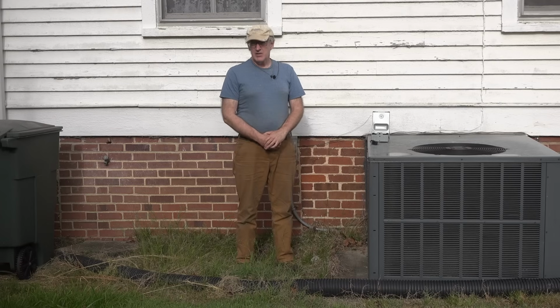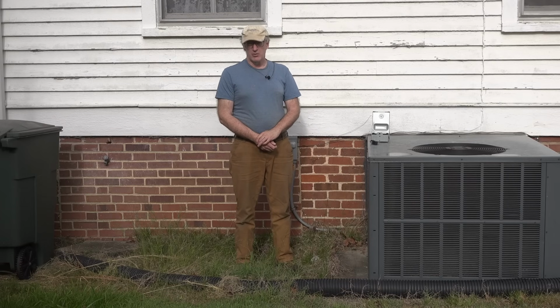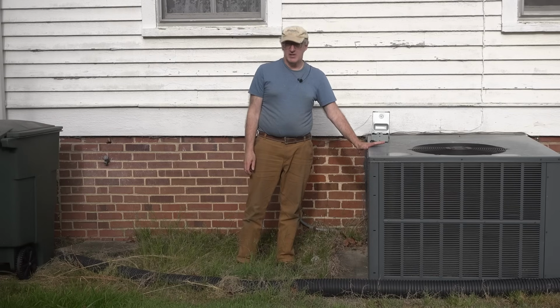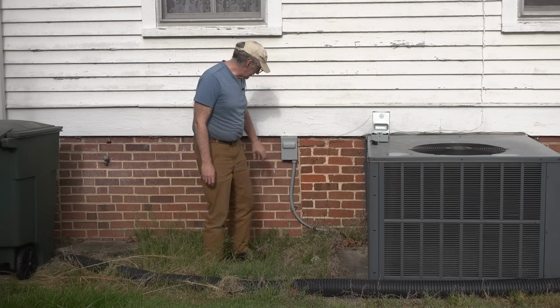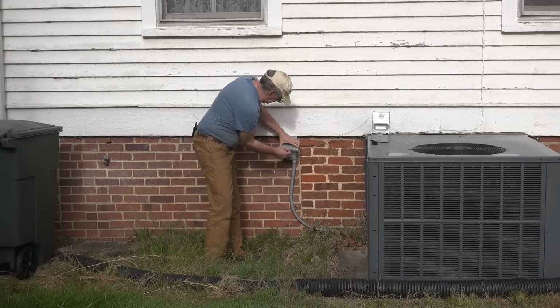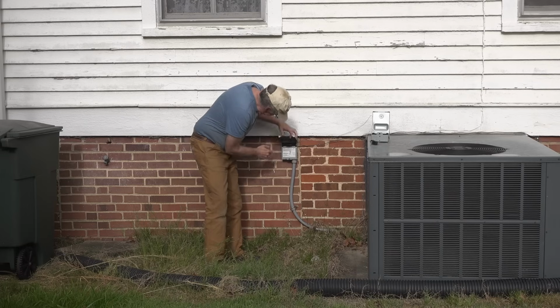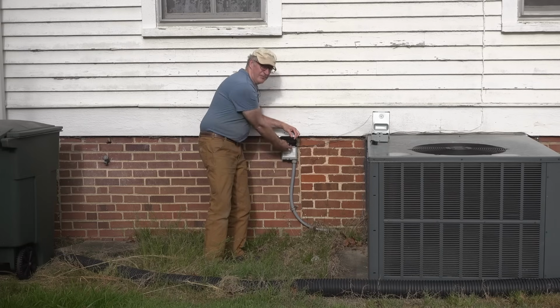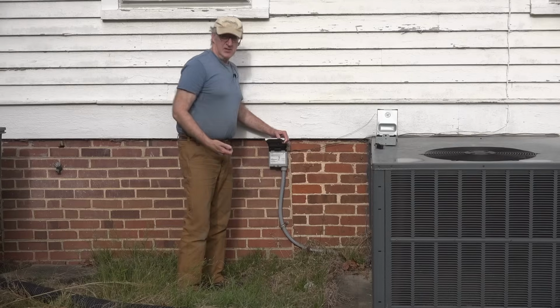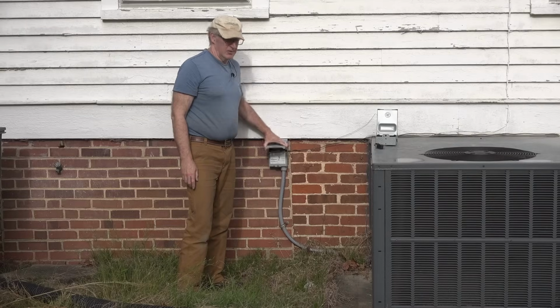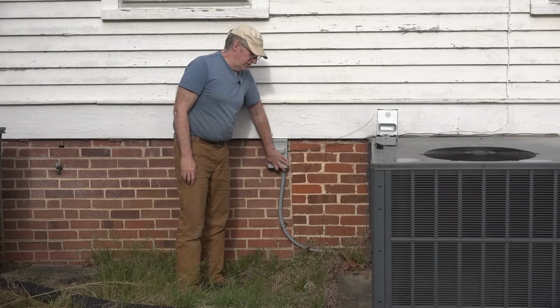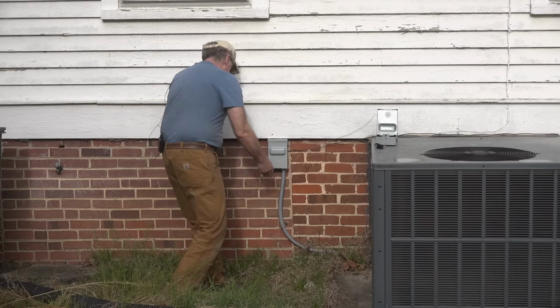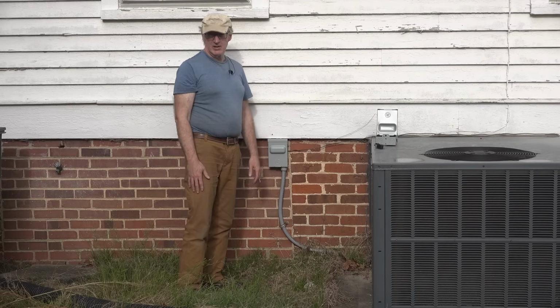But United States electrical building codes require that each one of these has an outdoor disconnect unit, and that looks like this. Inside this box there's a handle, and when you pull this handle out, it disconnects power to the unit, and that's done for servicing, so the air conditioning or heating guy can do his work without fear of getting electrocuted.